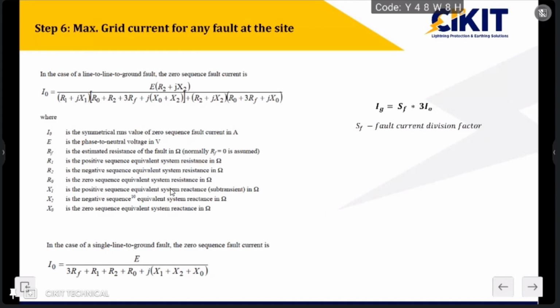So the most important thing is we have to calculate the grid current. Even though we know that the worst fault current will be at the three phase to ground short circuit fault, the three phase to ground fault is one of the rarest phenomena that won't happen frequently. So even though that is the worst case, since it won't happen in the power system, they consider single line to ground fault and line to line to ground fault as the worst cases in substations, and they have provided the formula for calculating this fault current for both the cases.